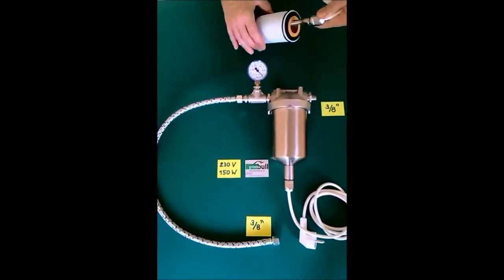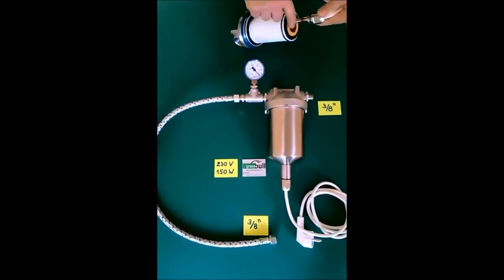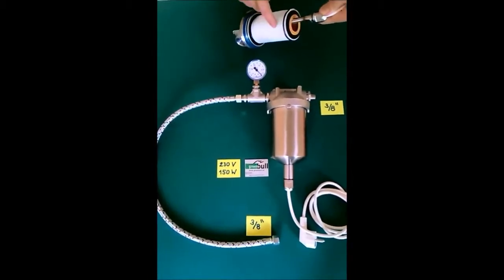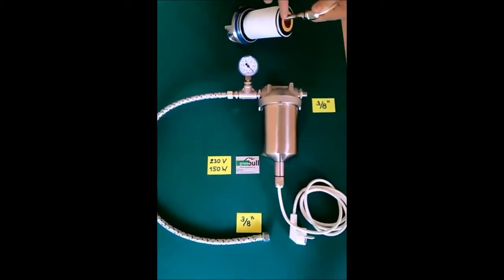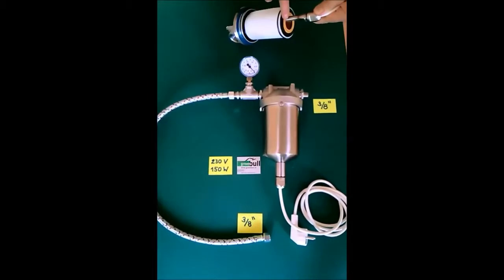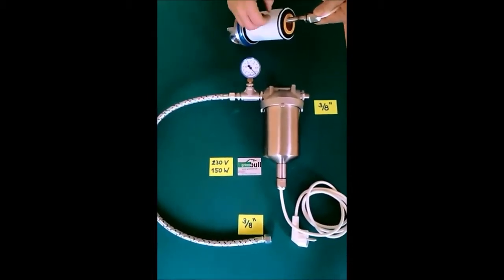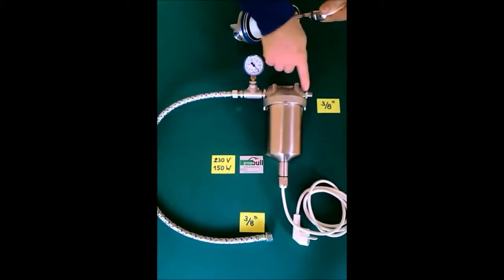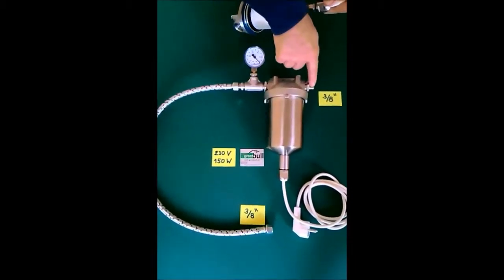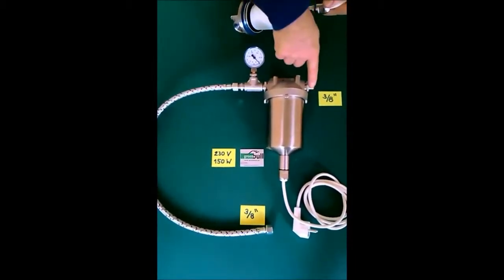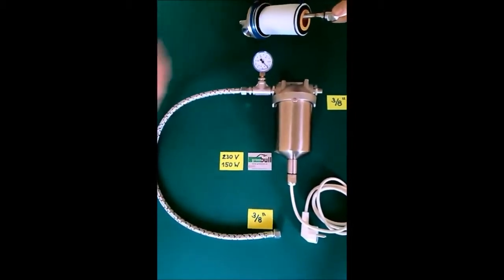This preheated oil will pass a yellow and then a white filter media. The yellow one is rated at 10 micron, the white one at 1 micron. Once it has passed the filter media, the filtered oil will then leave the system towards the burner.